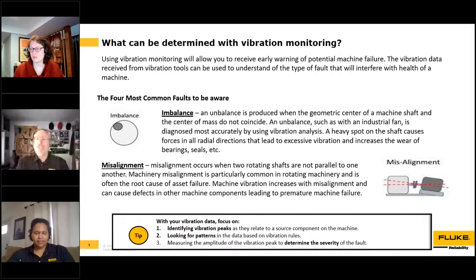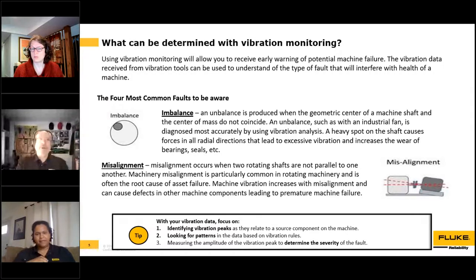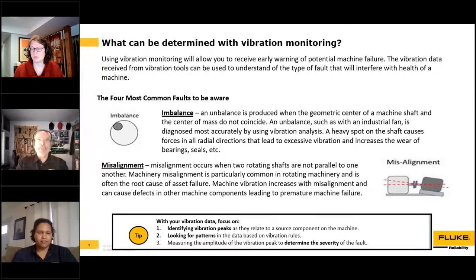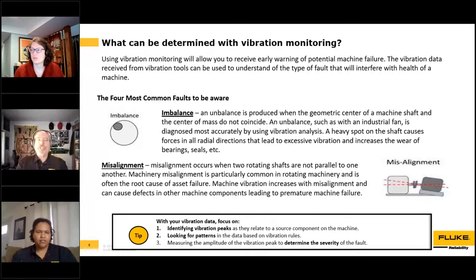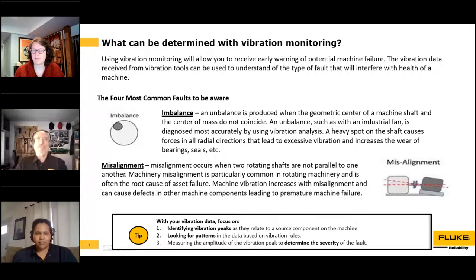Imbalance is where you have a heavy spot on the shaft — every time it rotates around, you feel that high vibration. Imbalance occurs in all radial directions, up and down and side to side. Imbalance and misalignment are really the two leading causes of high vibration. Unfortunately, a lot of customers — including myself when I was in the Navy — would replace the bearings and seals but ignore the root cause, which was imbalance and misalignment. That's a key point: we don't want to ignore the root cause.